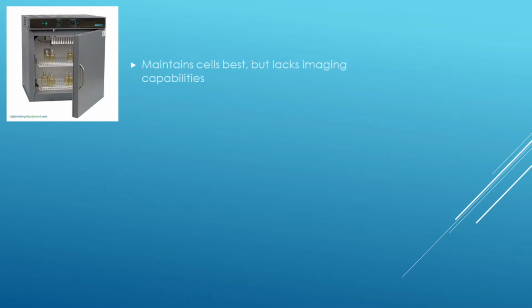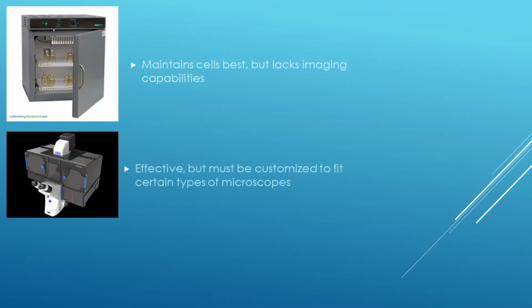Cells need this environment to survive long-term imaging, but it is not economically or physically feasible to make the entire room where the imaging would be done mimic the environment of an incubator that could supply this. So, to get around this issue, we bring the environment to the immediate area of the microscope. This is often done with an incubator that can surround the microscope, such as this, or an incubator that fits on the stage of a microscope, such as this.